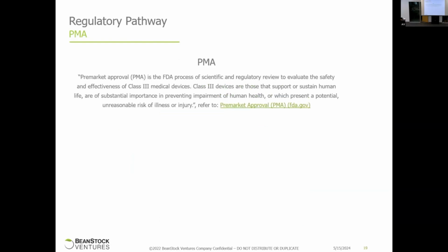PMA. So this is the most expensive pathway, but this applies to a lot of devices that don't have a predicate and that are highly innovative. So the pre-market approval is the process of scientific and regulatory review to evaluate the safety and efficacy of class 3 devices. So here, just note, class 3 devices are those that support or sustain human life, are of substantial importance in preventing impairment of human health, or which may present a potential unreasonable risk, injury, or illness.